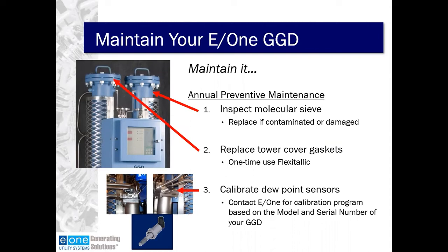We have the opportunity to isolate both mechanically and electrically. The dryer can be isolated and put in a safe mode with a purge gas, and then the preventive maintenance can be performed even during those periods if the generator were online. Obviously, follow all of the local plant safety requirements for that period of time. When we do remove those covers of the towers, there's a one-time use Flexitallic gasket, so that needs to be replaced during the annual preventive maintenance procedure.